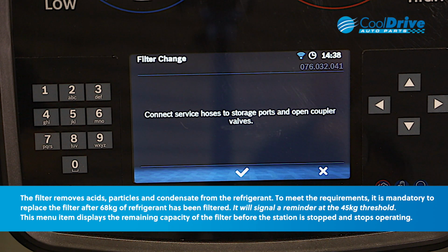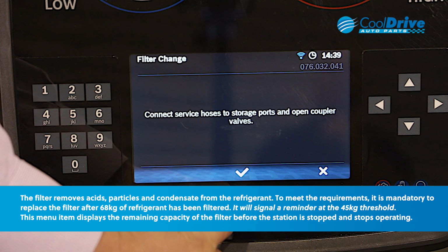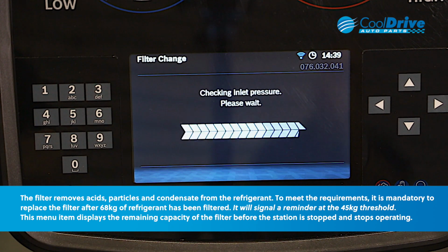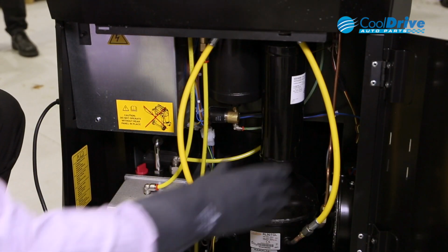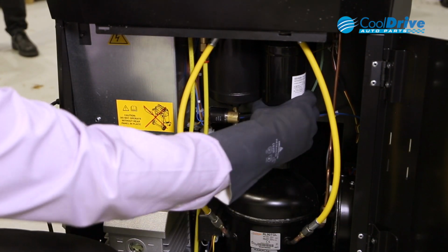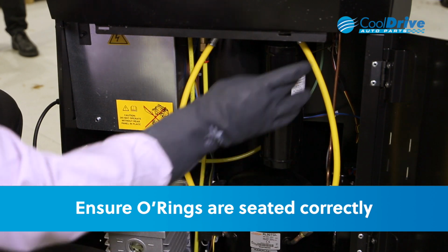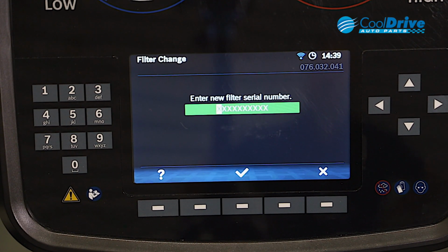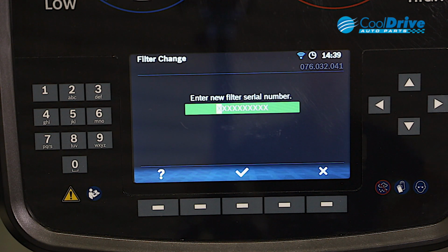We connect the service hoses to the storage ports and open coupler valves. This is to remove any refrigerant from the filter circuit. The filter assembly screws straight back on. Just ensure the O-rings are seated correctly. Once the refrigerant's been cleared from the filter circuit, we need to enter in the serial number on the replacement filter.